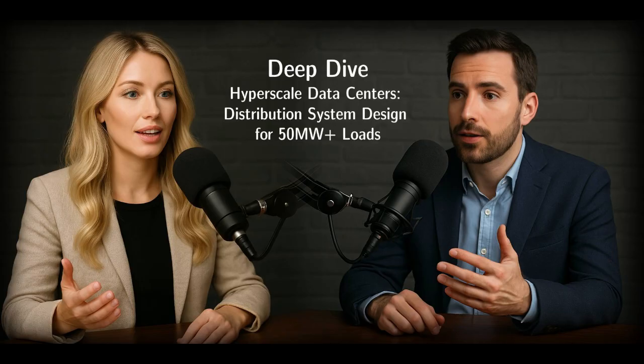Can you give us a comparison example again? The 75 megawatt case, 12.47 kilovolt versus 69 kilovolt. Sure. So for that 75 megawatt load, the 12.47 kilovolt option, maybe using 5 feeders, might have an initial capital cost of, say, $8 to $12 million. Seems cheaper upfront, maybe. But the annual energy losses could be around $450,000 per year because of the high currents. Over 20 years, considering the time value of money, the net present value of that option might be $18 to $22 million. Okay. And the 69 kilovolt option?